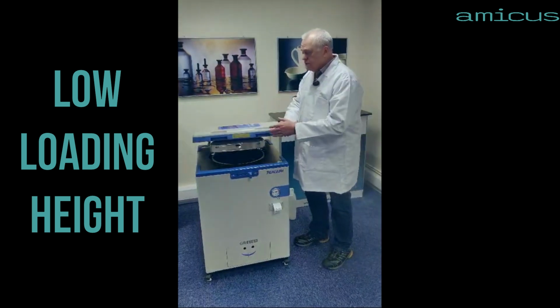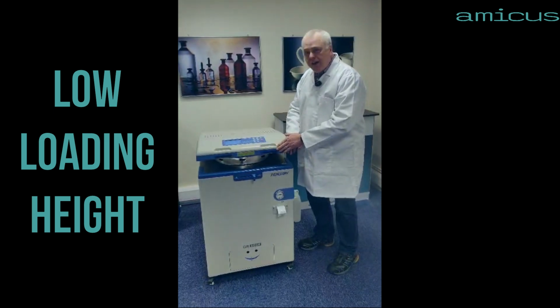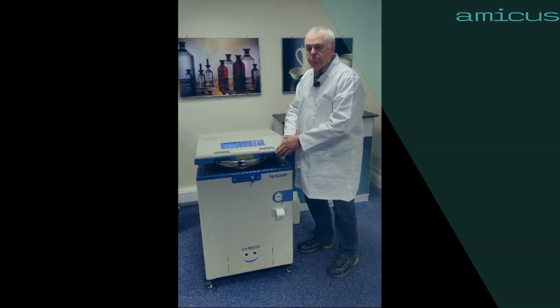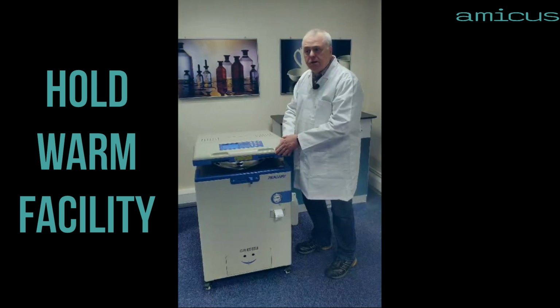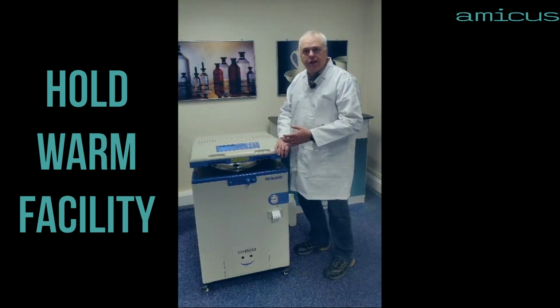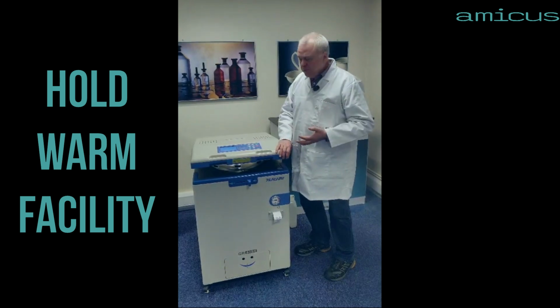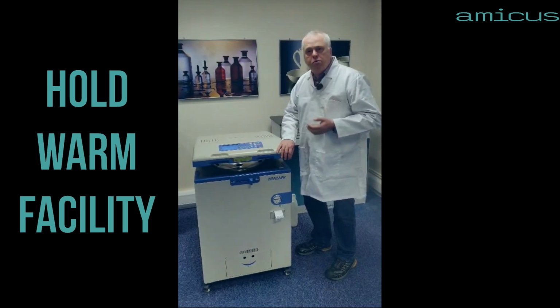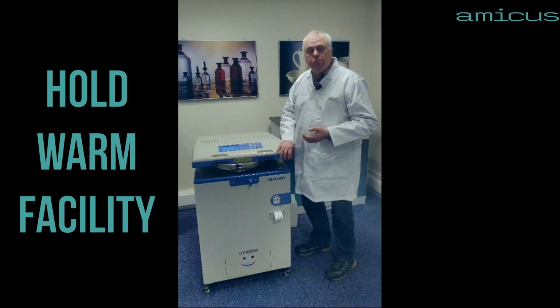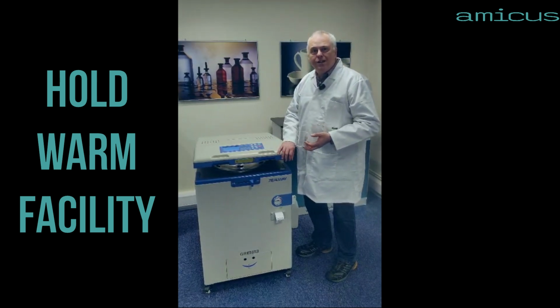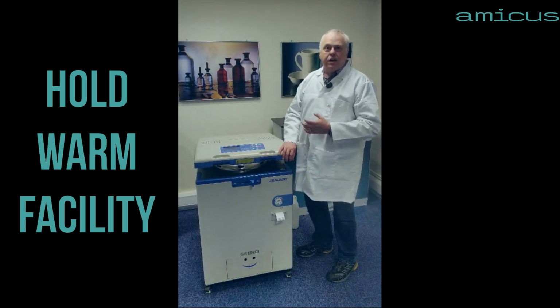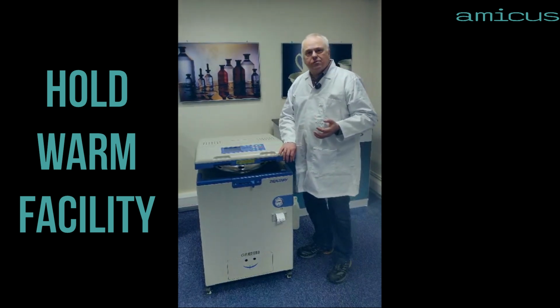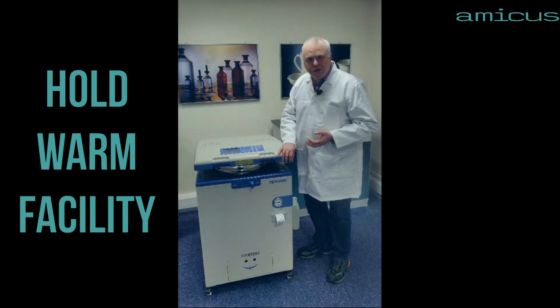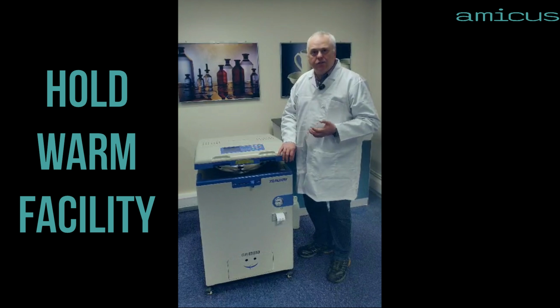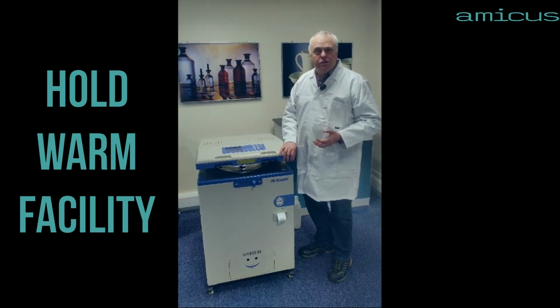As I mentioned, the autoclave is packed with features. One of their favourite features was the hold warm facility to keep media warm after sterilisation so that it's kept at the ideal pouring temperature. Up till now, they were having to remove the media from the autoclave and put it in an incubator. Whereas here, they've discovered that they can just leave it in the autoclave as long as they like. And they also loved the fact they could run the autoclave overnight, and then in the morning, the autoclave is full of pourable media just ready for them to get on with their prep work.